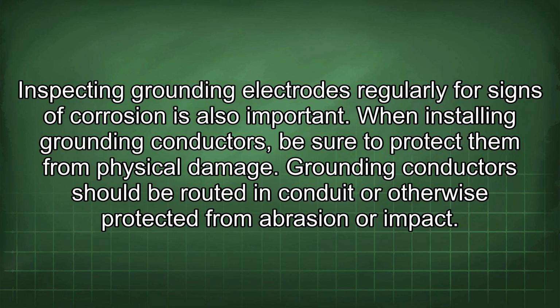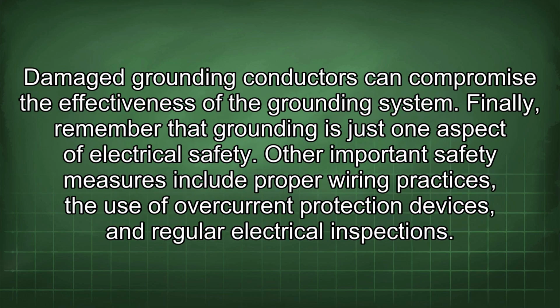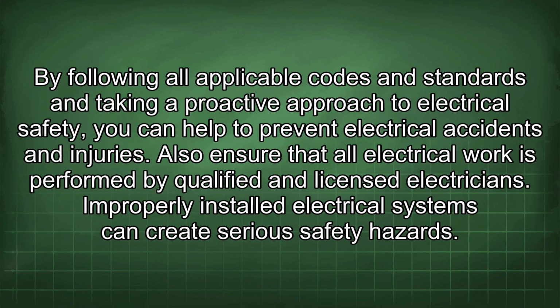When installing grounding conductors, be sure to protect them from physical damage. Grounding conductors should be routed in conduit or otherwise protected from abrasion or impact. Damaged grounding conductors can compromise the effectiveness of the grounding system. Finally, remember that grounding is just one aspect of electrical safety. Other important safety measures include proper wiring practices, the use of overcurrent protection devices, and regular electrical inspections.